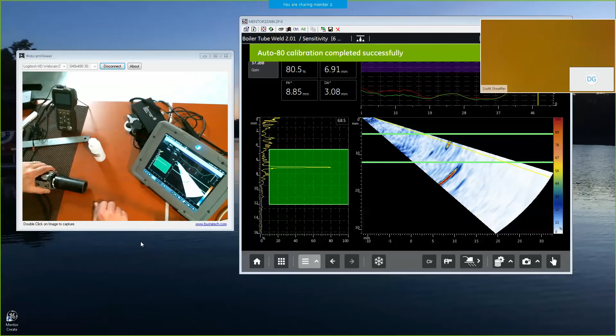Now we're going to set up and calibrate our scanner. It's already been set up with 314 millimeters, which would be the circumference of the pipe. I'm going to line up on the first hole as kind of an indication, and say start calibration. I'm going to rotate the pipe one full rotation - there's one rotation. Then I'm going to go backwards to check for backlash, back to my indication. There we go, and the encoder's been calibrated. So at this point, one good revolution of the encoder should be 314 millimeters.